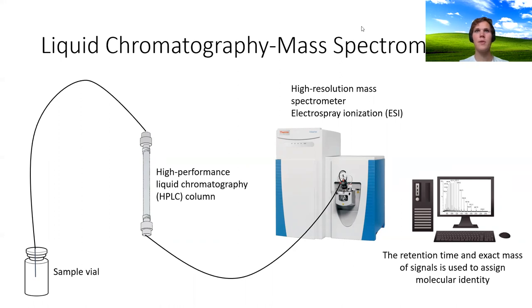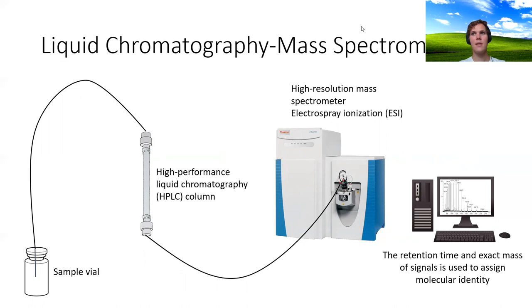As these ions come into contact with the mass spectrometer source, they get ionized by electrospray ionization, which is considered a soft ionization technique. We don't want to fragment these molecules — we want them detected as close to their form in the sample vial as possible. Using a high resolution mass spectrometer, we can infer the chemical composition of these compounds and identify the chemical formula based on their high resolution mass. Using the retention time and the exact mass of the signals, we can identify molecular identity.